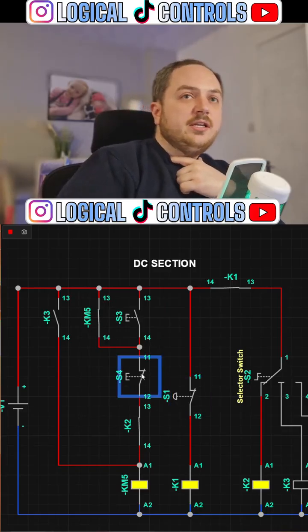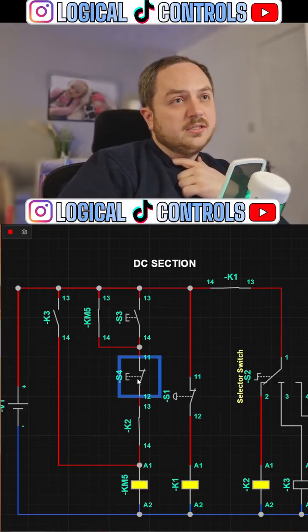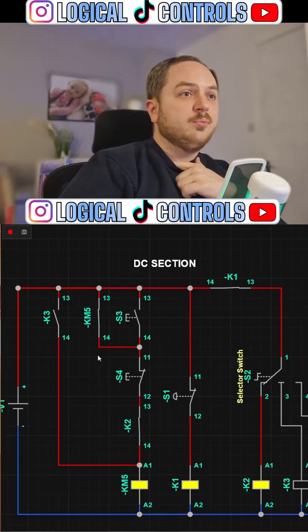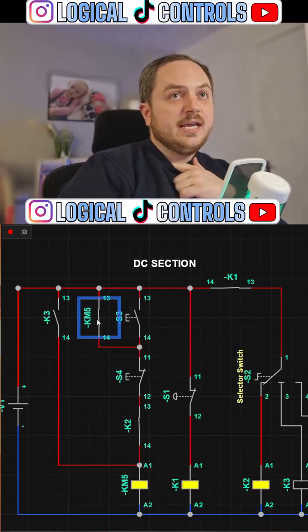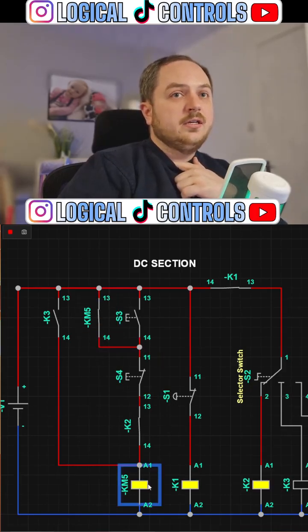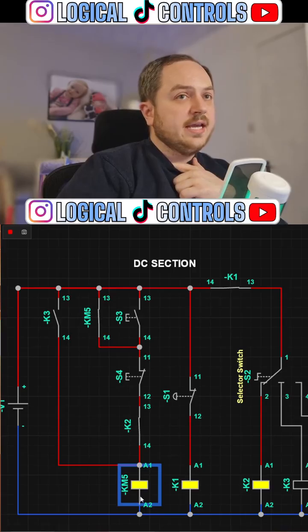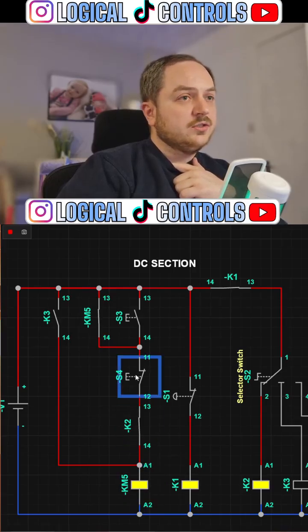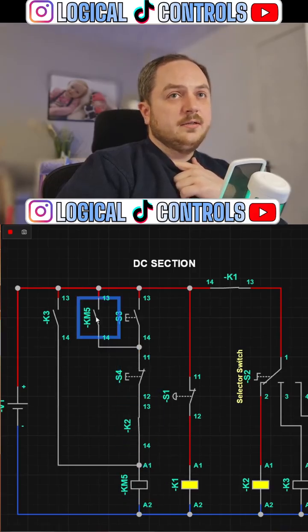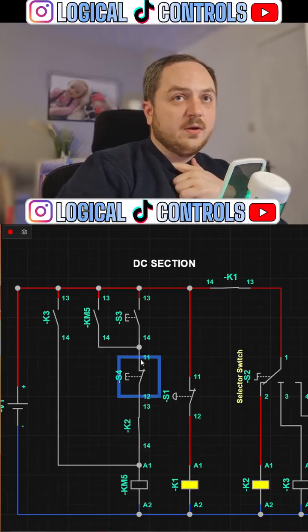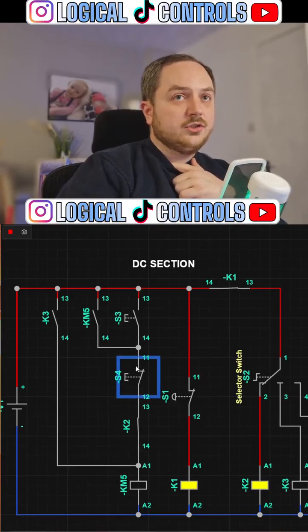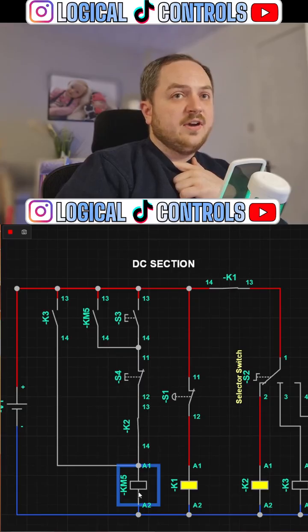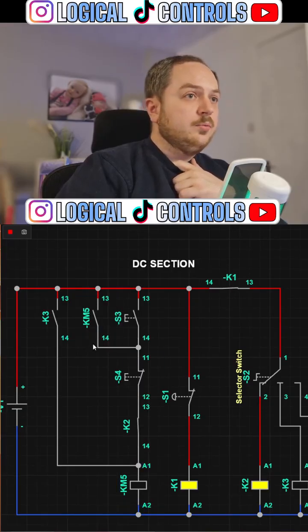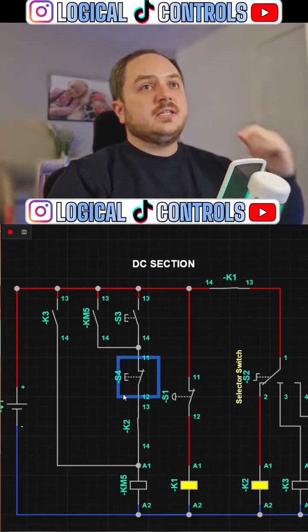And you need a stop button as well as a start button because you need some way of breaking that latch. So KM5 at the minute is held in, you've got no way of de-energizing KM5 unless you press that stop button. So press that - the positive that was making its way down here, because I've opened that, stops here. KM5 de-energizes, and then that opens the contact back up. Hopefully that makes sense for everyone.